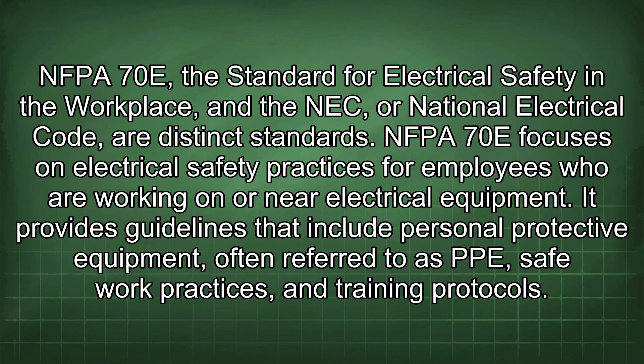NFPA 70E, the standard for electrical safety in the workplace, and the NEC, or National Electrical Code, are distinct standards. NFPA 70E focuses on electrical safety practices for employees who are working on or near electrical equipment. It provides guidelines that include personal protective equipment, often referred to as PPE, safe work practices, and training protocols. The NEC, in contrast, focuses on the installation, maintenance, and the proper use of electrical equipment and systems. Its main goal is to minimize electrical hazards through proper installation and maintenance.